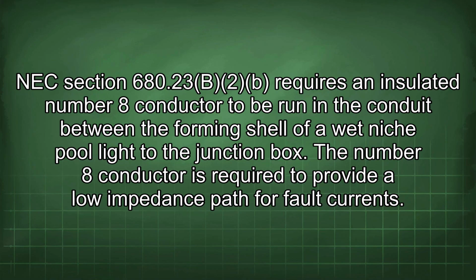NEC Section 680.23(B)(2) requires an insulated number 8 conductor to be run in the conduit between the forming shell of a wet niche pool light and the junction box.